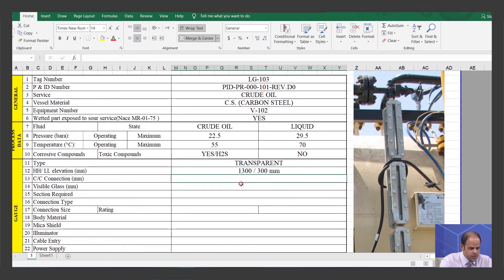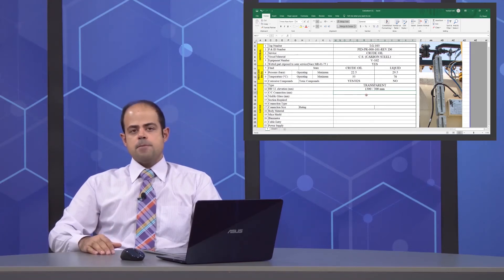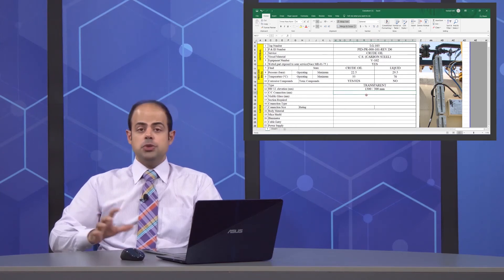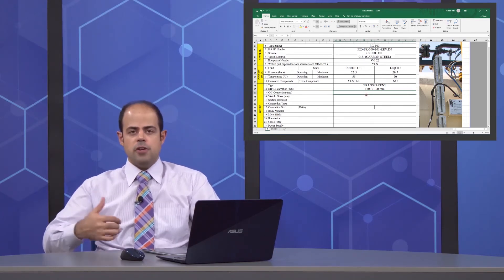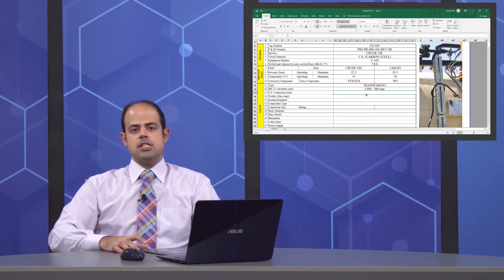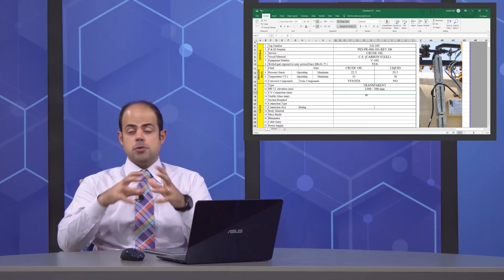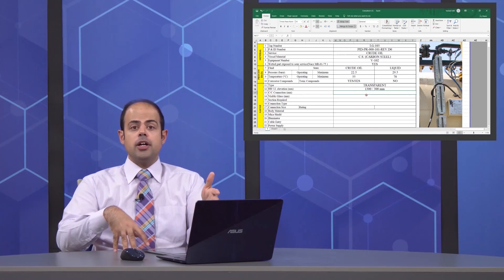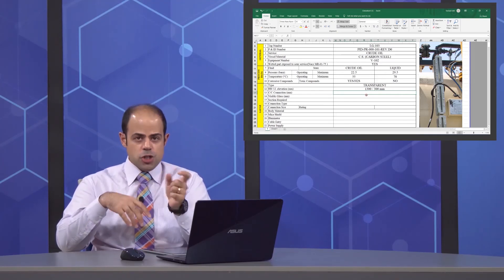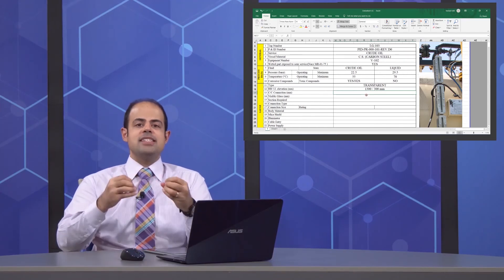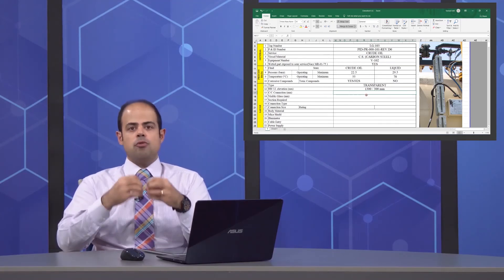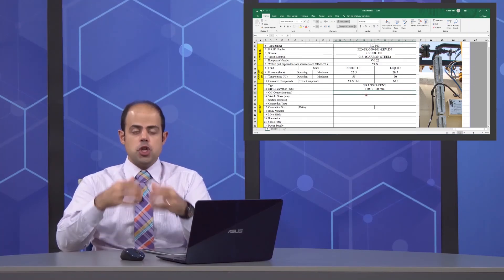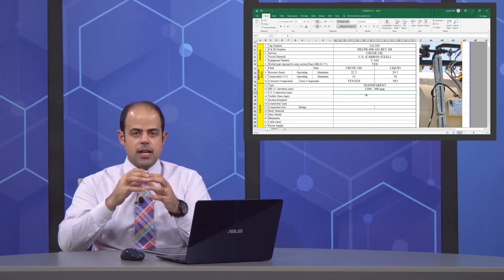Next item about the center to center connection. You can, for example, use some catalogs or the manufacturer's data sheet to understand about the C2C and visible glass too. But if you remember, I wrote something on the whiteboard in previous episodes. The thing that can be suitable for this item must be a thing that all parts of the process level must be totally clear and visible. The high-high part here is 1300 and the least elevation or level is 300. If you subtract these two things, you reach 1000 millimeter. So it means the part of the sight glass must at least have 1000 millimeter visibility to show all these things consecutively and without any gaps or interruption between the parts.